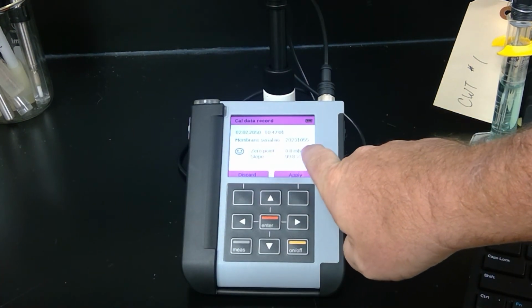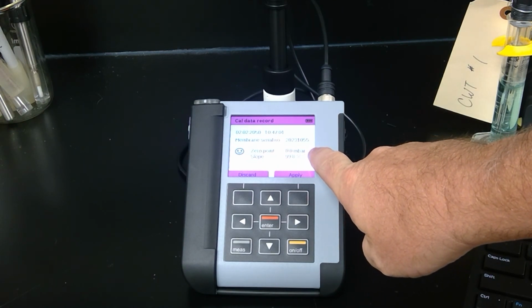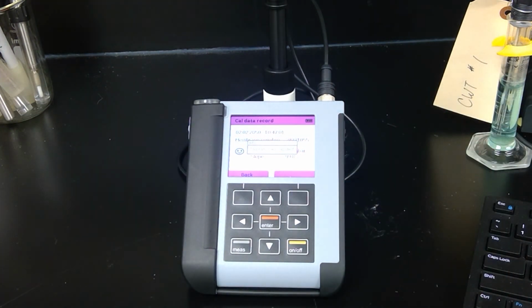So as you can see here, it's set our 0 point at 0 millibar. Our slope is 99.8. We have the smiley. We hit apply. And the calibration is complete. And the SE340 is ready to go.